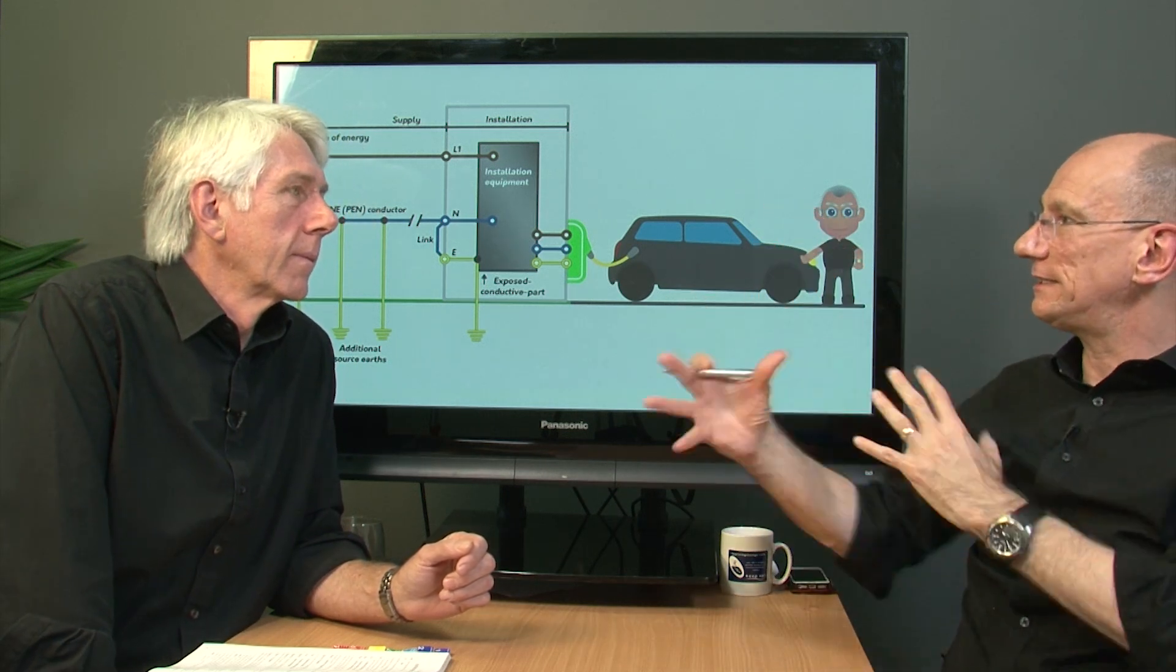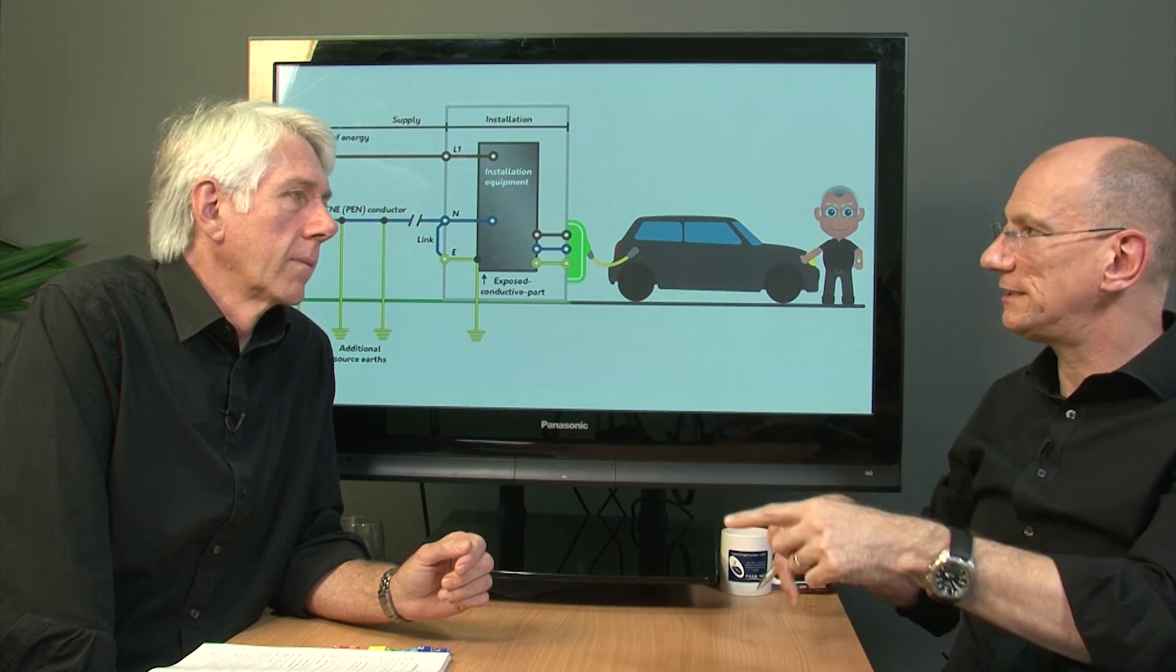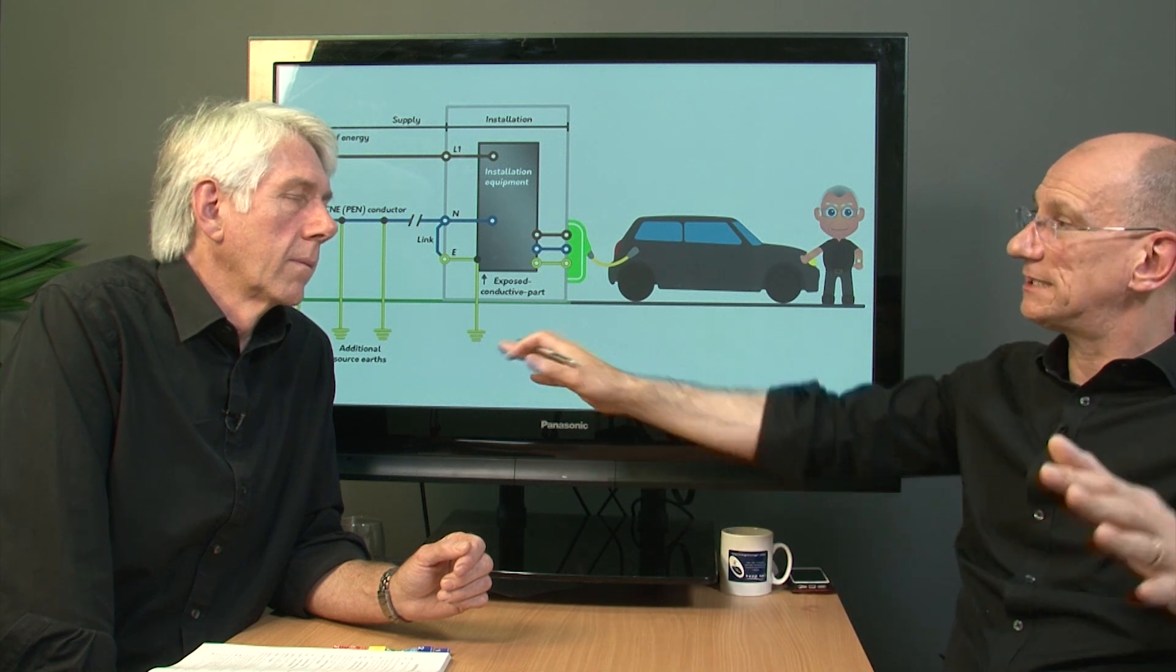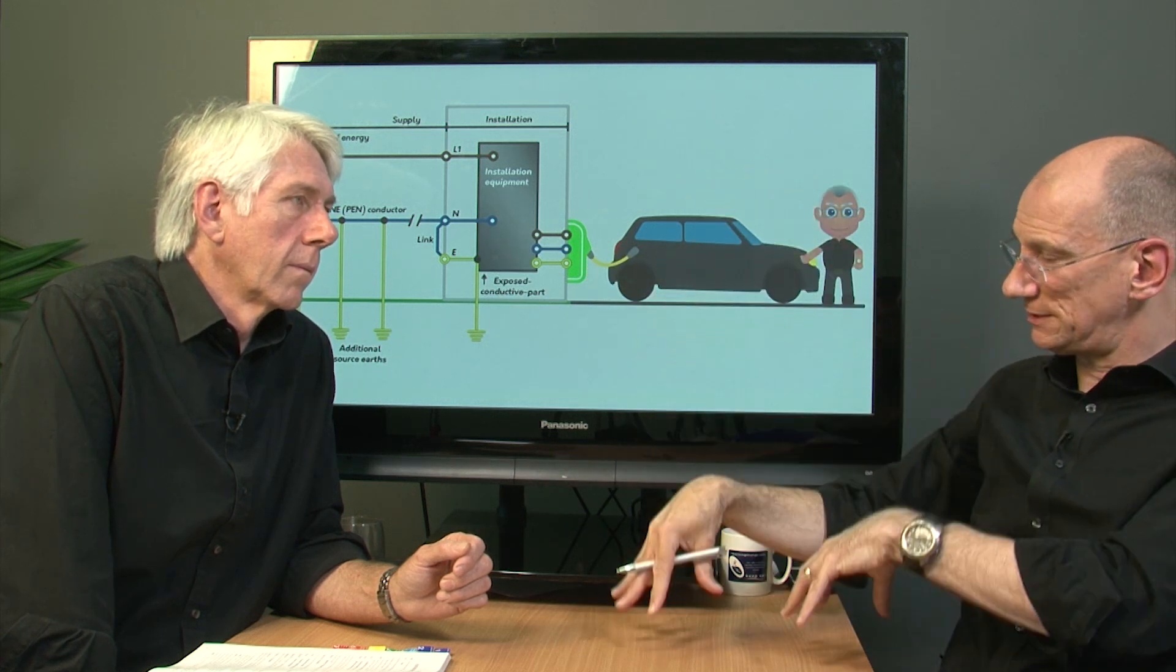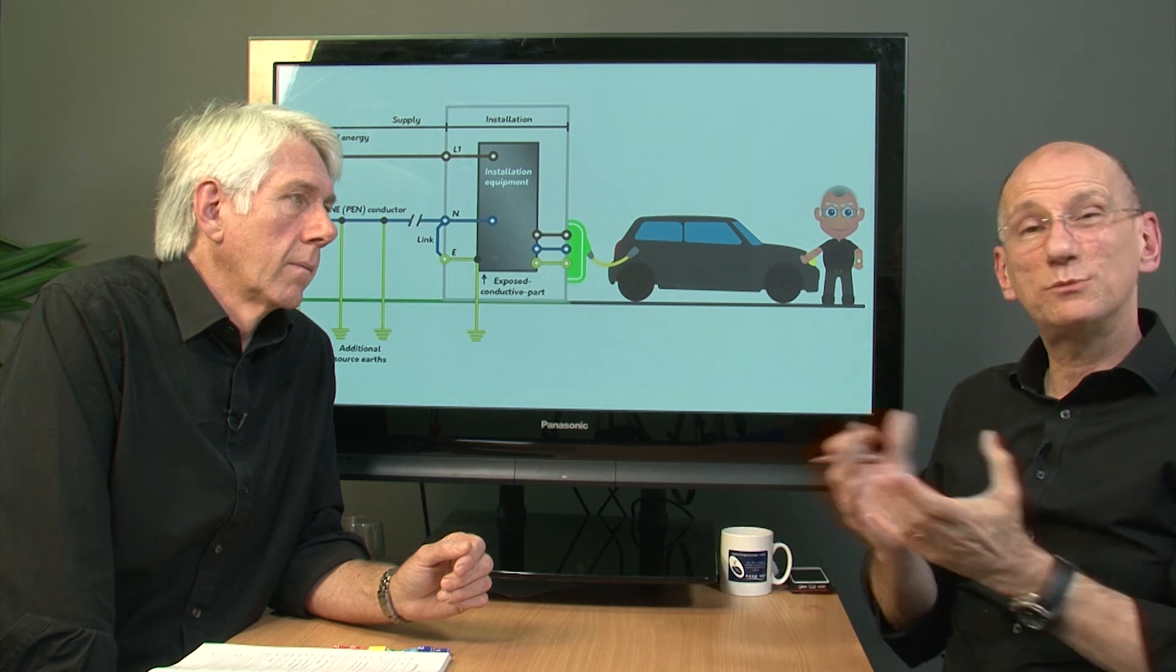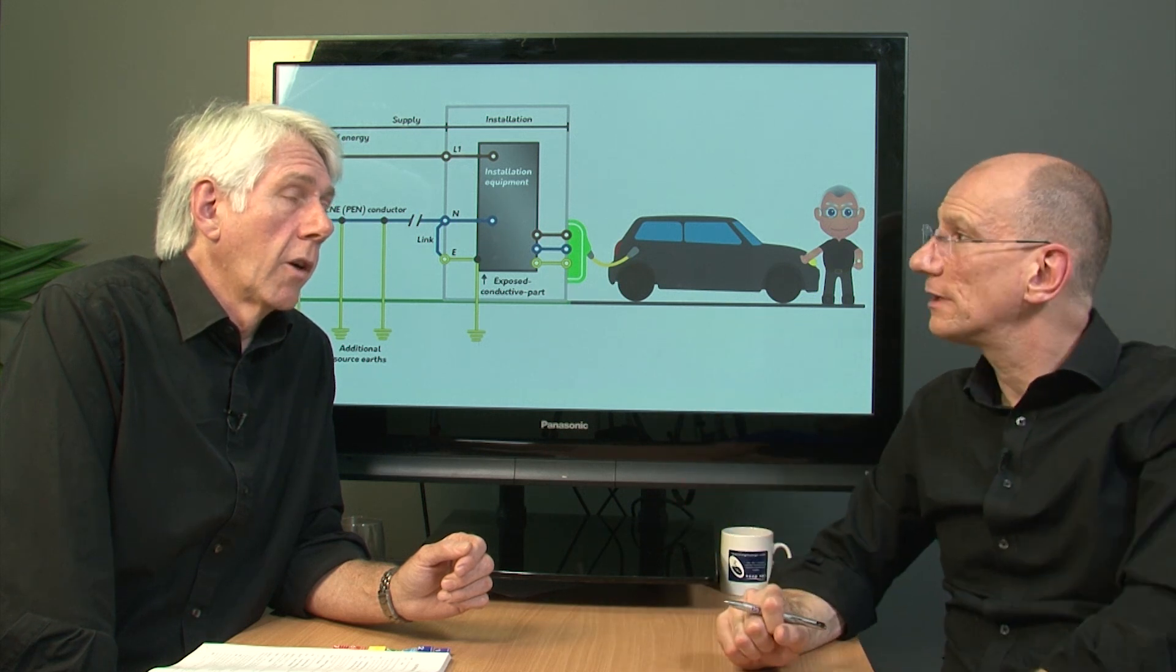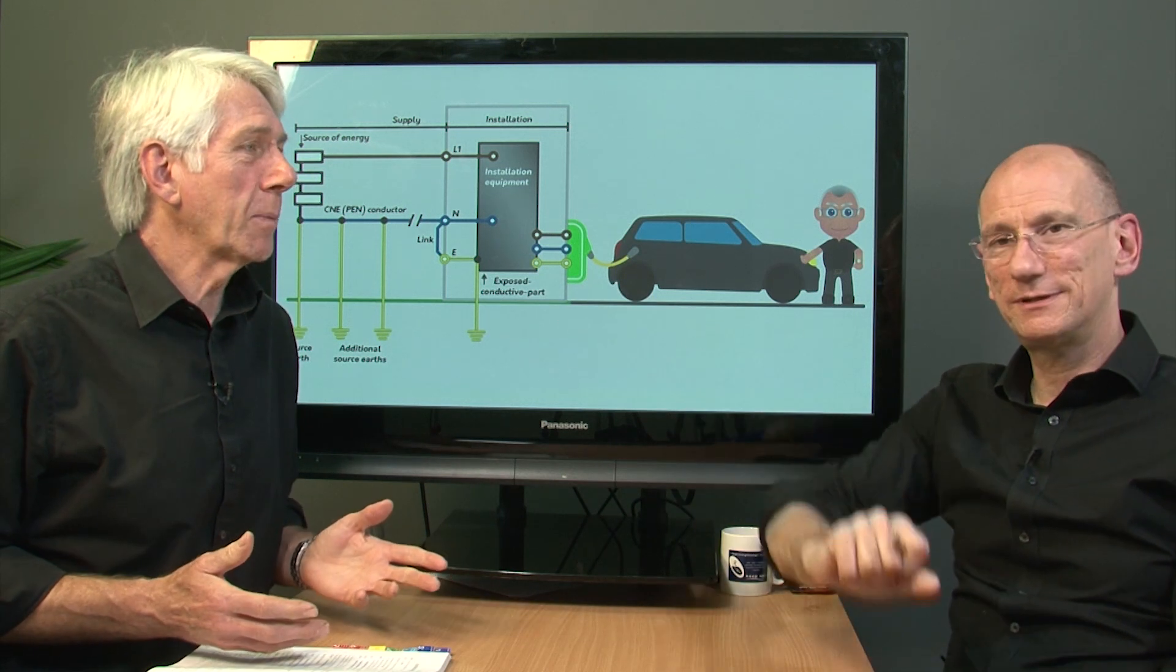The other thing I want to mention was that separating these systems, so this is one of the things that gets brought out on the course, is that typically on a domestic property, you've got a brick-built house. So you could do the TT arrangement. But if you're working on an industrial site or a scenario where you've got a metallic building, steel stanchions in the ground and you give yourself a couple of three metres, so if you've heard this rule here, you've got a little distance, so you can't physically touch the two-component parts. Any drop-in... If you have an open-circuit neutral, the voltage will rise. You can have a difference in... But you've got this steel work going into the ground. This is going to have a massive impact on the electrodes. So your one little rod versus all of that just doesn't make sense, really. So people are looking at this and you need to watch this space to see whether we're going to continue connecting to PME by these special safety devices built into the device charging point or not and just to see if we can make this even safer. So those conversations are happening? They're happening. I've seen a bit on the internet and I've had conversations with various people. It's... things are moving. Things may change again.